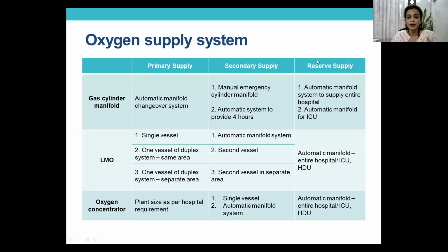Now, the most important thing is when you have your liquid medical oxygen, there are two things that you have to remember. You can either have a single vessel or you can have two vessels. When you have two vessels, you can have both in the same location, or one vessel in one area and the other vessel in another area. So there are three things that you have to remember. If it's only a single vessel, then your secondary supply certainly will have to be an automatic manifold system. You may not use it at all, but you need to have that 24 hours pressurized.